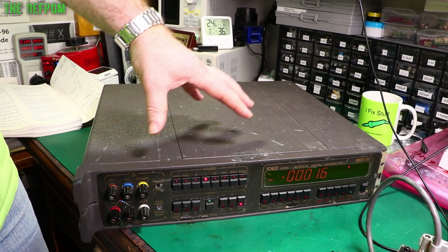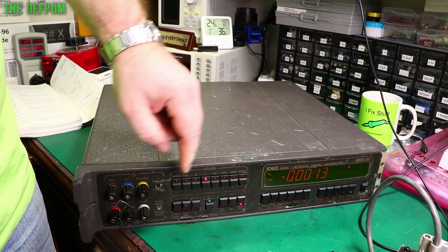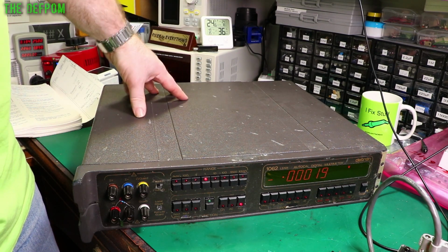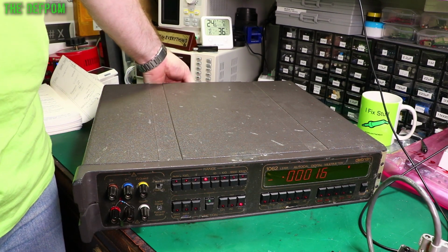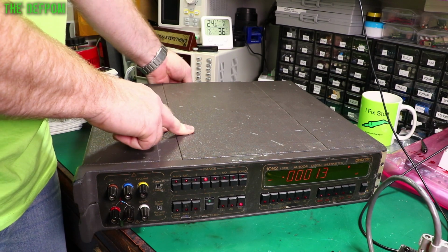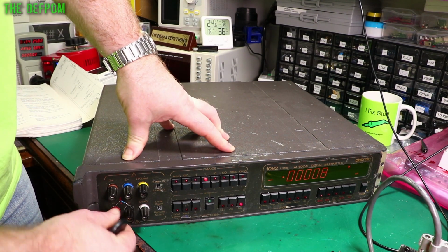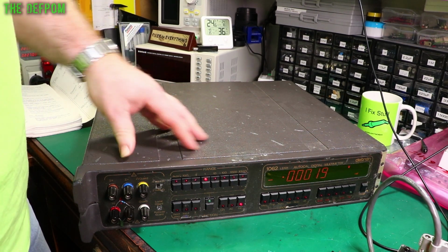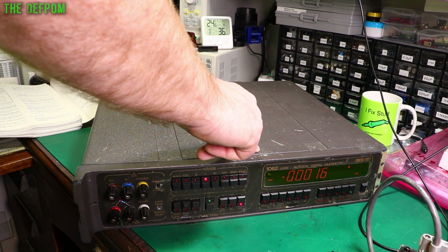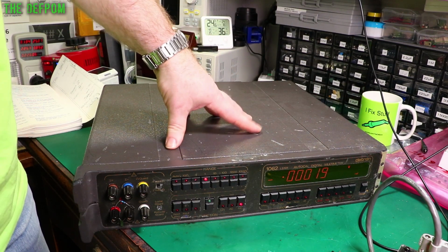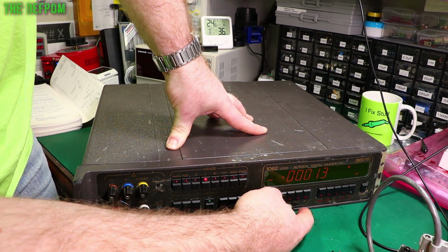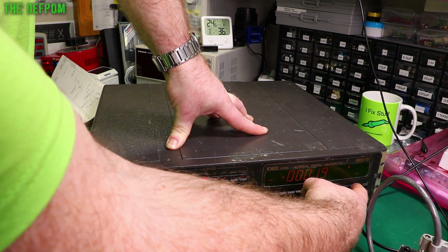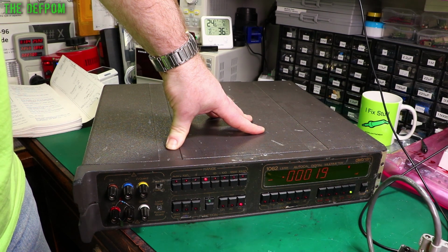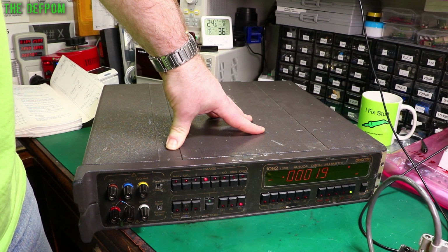Alright, now it says to do 1 volt range, no filter. I've got to go to calibration mode, so I've got to turn the key switch on. And I've also changed the resistor here to be a 1 megaohm instead of a 10 megaohm. Now what it says to do is, now the calibration key is turned on, you see CAL on the display, and select linearity, which is over here. So I've got to push this button, let it do its thing, and the light will go out when it's finished.